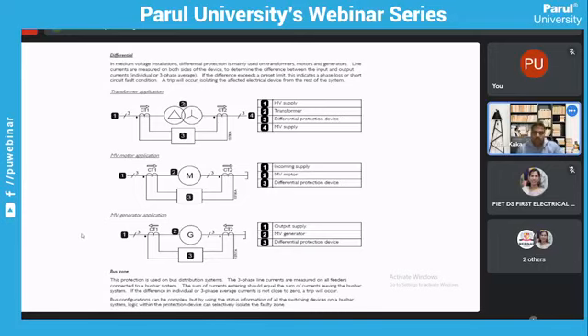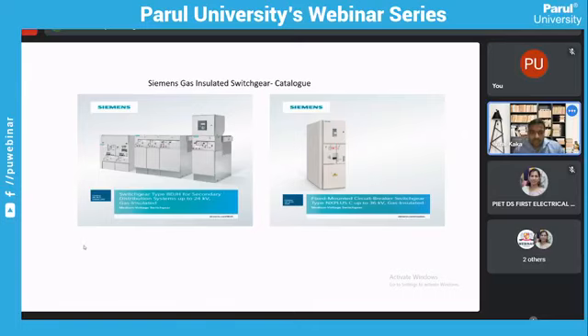So that's what the concept of bus zone or bus bar differential is. Again, these are some of the gas insulated switchgears. 8DJH type of secondary gears and NX Plus C, which you are seeing on the right side. NX Plus C falls into the advanced primary switchgear category, while 8DJH is predominantly used in the secondary market. Also, it has a block type configuration, which we normally call a ring main unit. It has a single tank configuration and it can be straight away deployed anywhere outside. So that's why I have attached a catalog and I can share this one at the end of the presentation meeting as well.